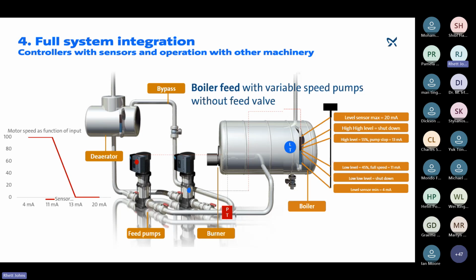As an example, on the left, we've got our motor speed set as a function of input from the level sensor, where we've got 100% speed running out of the pumps when the level is set to low, and when it is full and we're up to 20 milliamps, or 13 to 20 milliamps, we're reaching the required level of the system, the pumps are then not running and we're not feeding in more water.